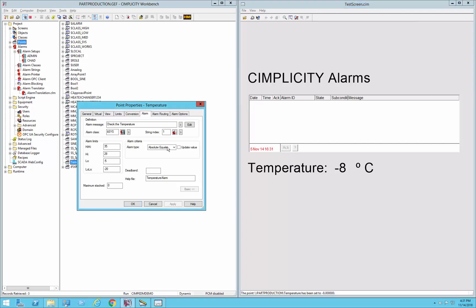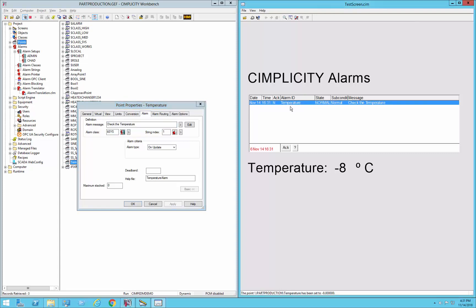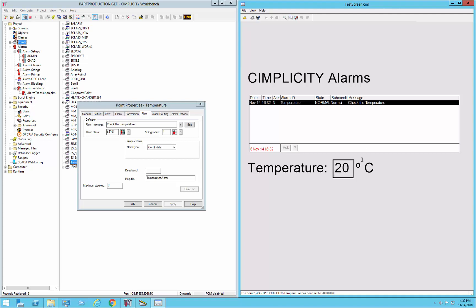Next we're going to skip down to the on update alarm, which is again a very simple alarm. In this case, you do not even need any limits because essentially you will have an alarm whenever the value changes. So you can see it is currently in a normal state over here because we switched into that alarm type. But normally that's not an alarm until it changes. So if I change this now to 20 degrees, it still keeps the state of normal, but it basically says you had a value that changed and now you need to acknowledge that. It will go back and that will go away.